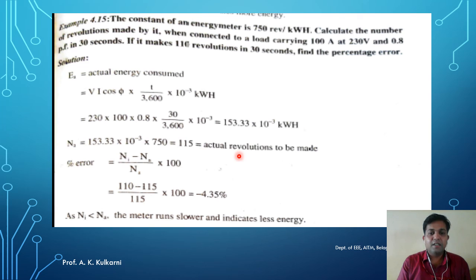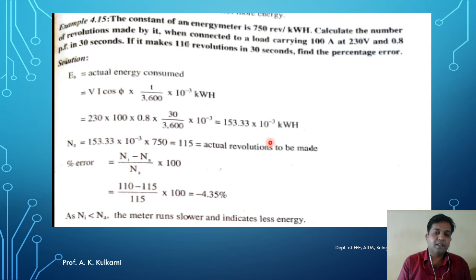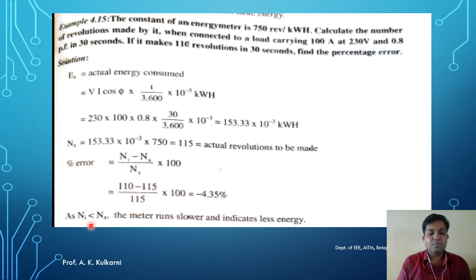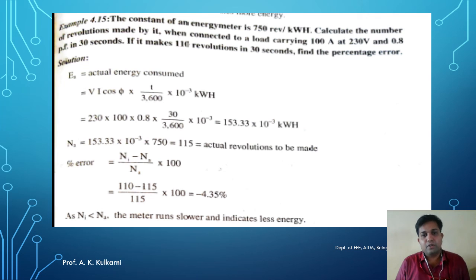The actual revolutions to be made are 115. When the meter makes only 110 revolutions, the percentage error = (110 − 115) / 115 × 100 = −4.35%. The indicated revolution is smaller than the actual revolution, meaning the meter runs slower and indicates less energy. The meter needs to be recalibrated so that the indicated energy equals the actual energy.